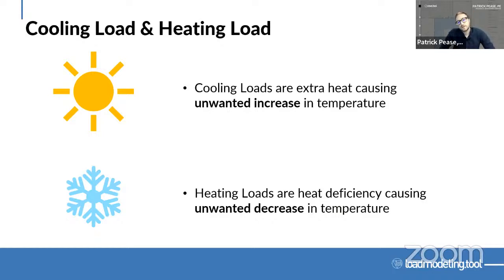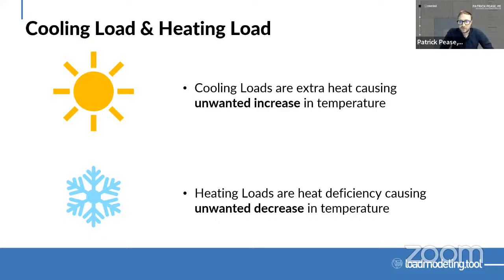Cooling load is heat causing an unwanted increase in temperature — and the word 'unwanted' is important. For example, if we have fin tube radiators in a room that are only on during the winter as designed, that's not unwanted; it's the desired heating. That wouldn't be considered a cooling load. But if poor controls caused them to run during the cooling season, we'd have to accommodate that in the cooling design — though a much better practice would be to fix those controls.